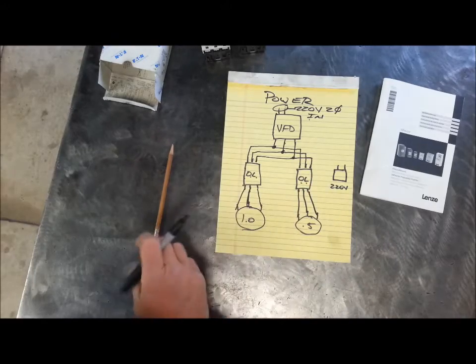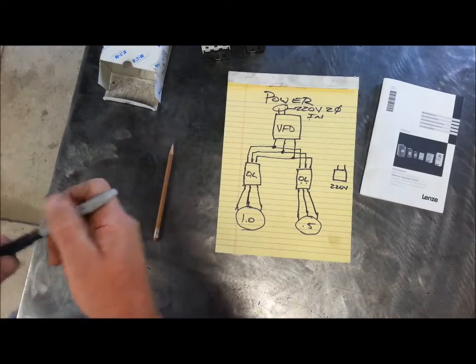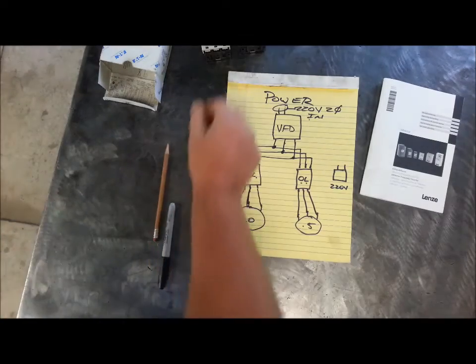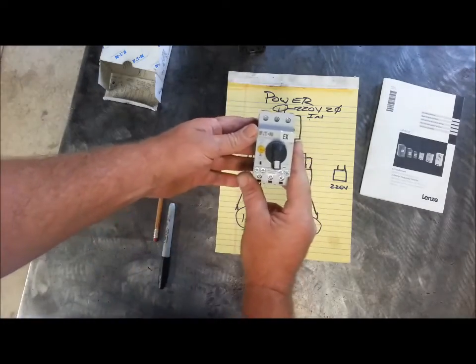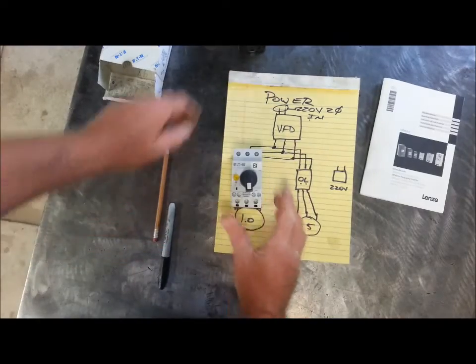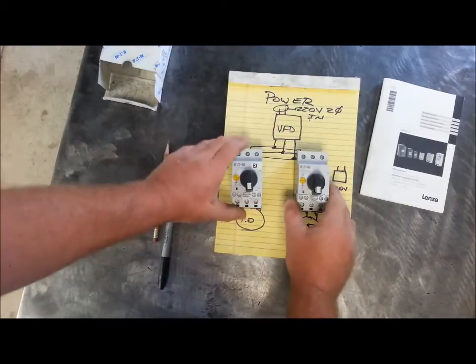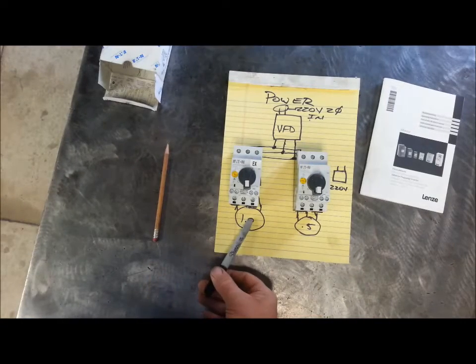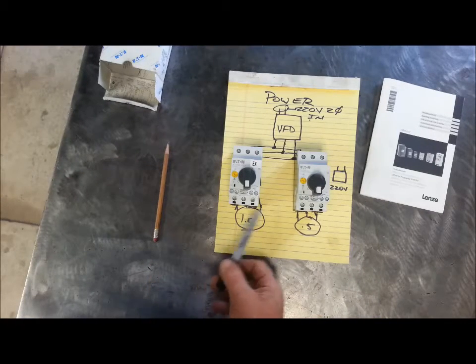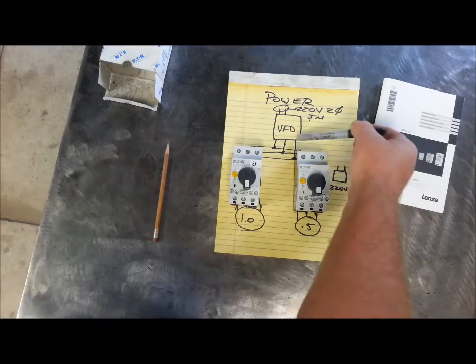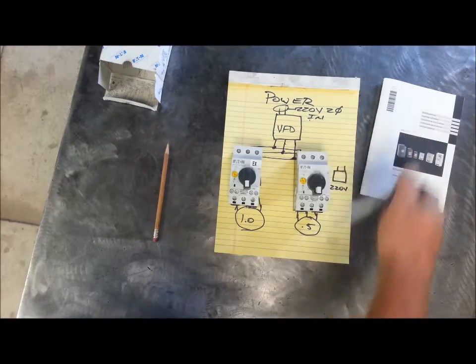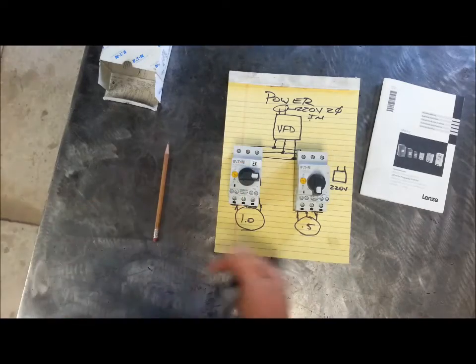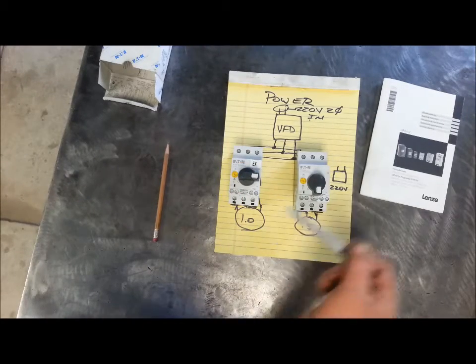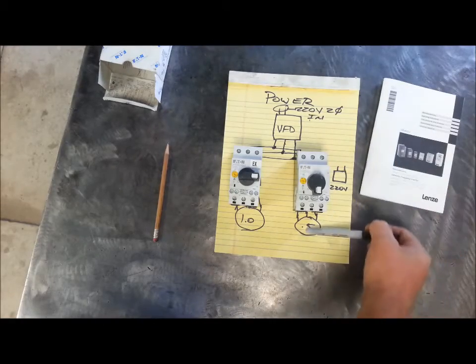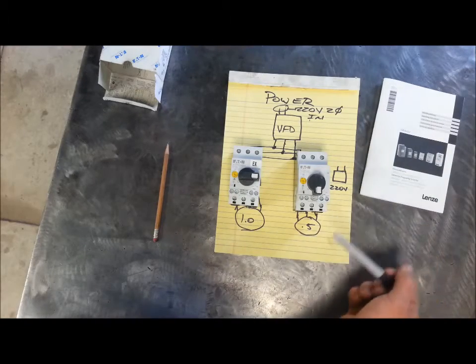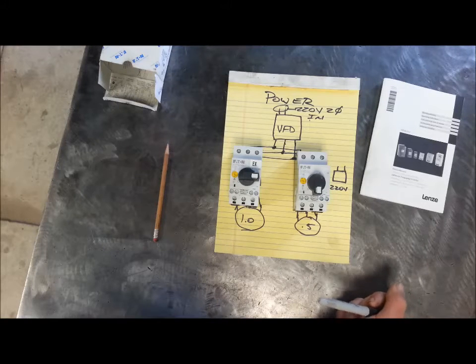Now, we've protected each motor for overload, but the VFD doesn't know that. If we lose a motor or overheat a motor here, the VFD doesn't know. All it knows is its output right here at these three lines. So if we trip here and this motor goes into fault, the VFD doesn't know that, because all it's running now is one motor, and it doesn't know to shut down and it doesn't know a fault condition exists.